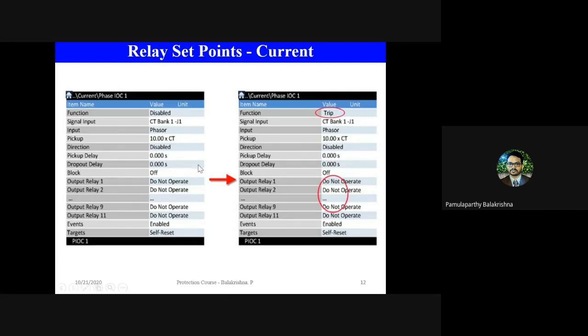Then you have something called delay. What this delay means is that the moment this function sees an overcurrent of this magnitude, if you do not configure any delay, it will straight away trip the breaker. But if you set some delay in milliseconds, it will wait for that many milliseconds before sending the trip signal to the breaker. That is defined as the pickup delay. Basically, it's the time the relay has to wait after it has seen this much current before executing the trip command to the breaker. It is used for security purposes. Sometimes there is a malfunction in the signal or measured quantities, or a temporary spike in the current. In order to avoid unnecessary trips, this delay configuration is generally provided.